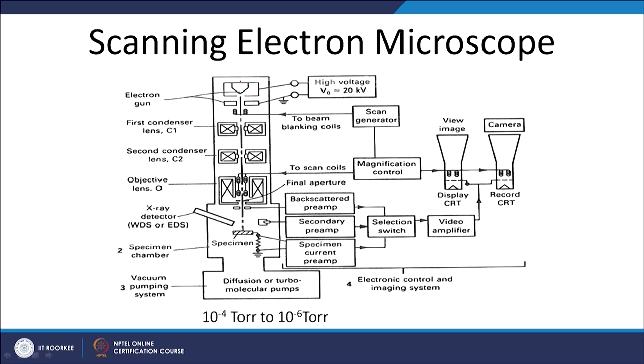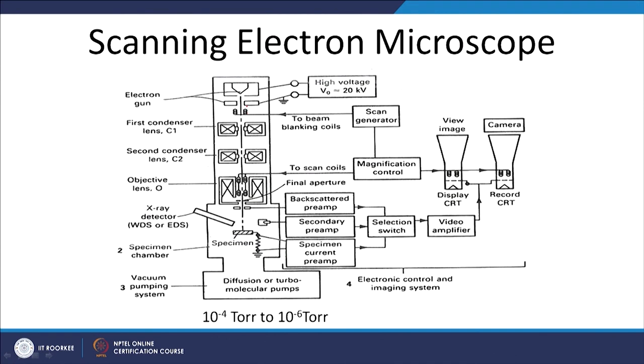In an optical microscope we use a lens to collimate the beam, but in an electron microscope we cannot use lenses — instead we use electromagnetic coils which serve as lenses and collimate the beam. The first condenser lens C1 collimates the beam, the second condenser lens C2 further collimates it, and finally the collimated beam falls on an objective lens O, which is connected to a scanning coil, which in turn is connected to a magnification control unit and scan generator.